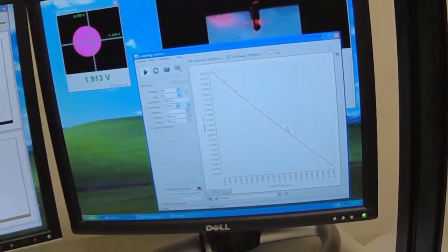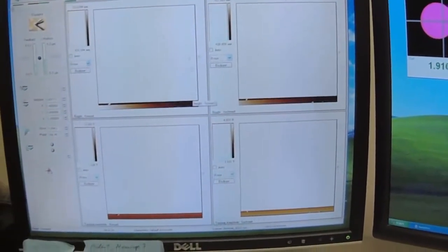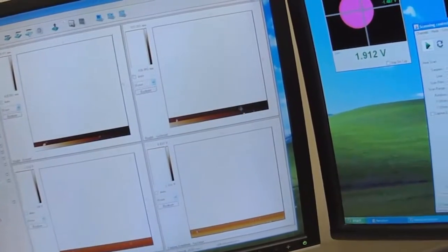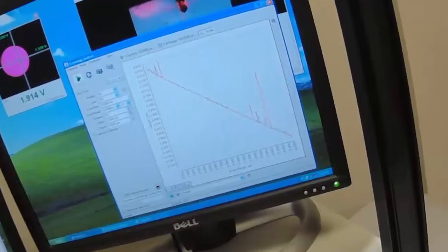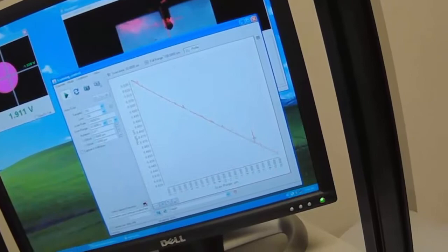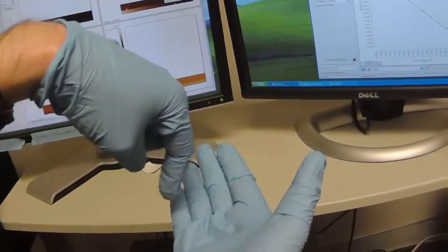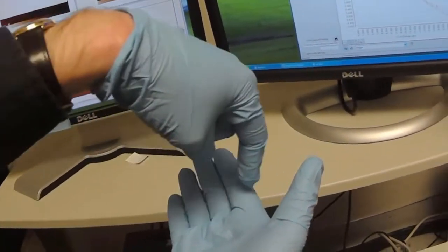Each scan, this is line by line, the profile for each scan, and then this is the image that's being built up as we scan X forward, X backward, and then we move up one in Y. See, this is Y. Brightness means a high object. Darkness means a low object. In this case, we have a very flat surface. That's our glass slide. And every now and then we have these bright spots, which in our profile look like spikes. If everything's tracking well, the forward and the backward profiles should look similar, and it looks very similar. They're shifted a little bit, which you might expect as you go in one direction and then turn around and go the other direction. There's going to be some slapping, I guess you'd call it.